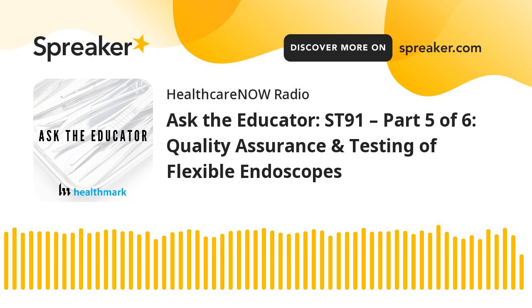So what ST91 basically says is that we want to emphasize that you should have the best quality of water coming into your endoscope processing areas to allow those high quality processes to be successful. So we have strong recommendations to monitor and control the water supply that comes into both your endoscope processing sinks, where you do the cleaning, rinsing, and leak testing, but also to any equipment like your AERs. And you want to make sure you have the best quality water going into those as your facility can have, and that you need to control that.